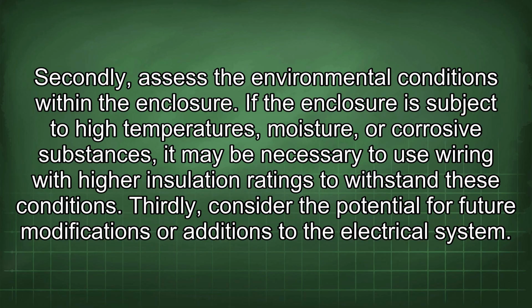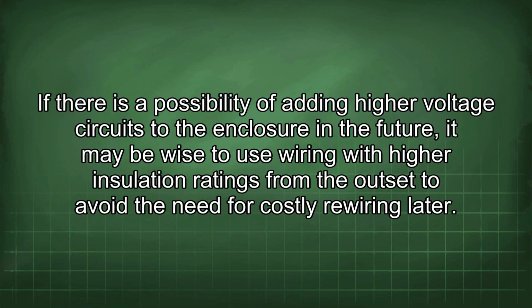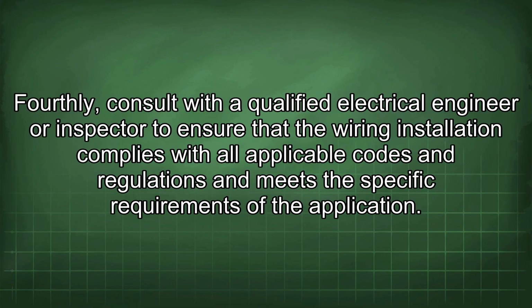If the enclosure is subject to high temperatures, moisture, or corrosive substances, it may be necessary to use wiring with higher insulation ratings to withstand these conditions. Thirdly, consider the potential for future modifications or additions to the electrical system. If there is a possibility of adding higher voltage circuits to the enclosure in the future, it may be wise to use wiring with higher insulation ratings from the outset to avoid the need for costly rewiring later. Fourthly, consult with a qualified electrical engineer or inspector to ensure that the wiring installation complies with all applicable codes and regulations and meets the specific requirements of the application.